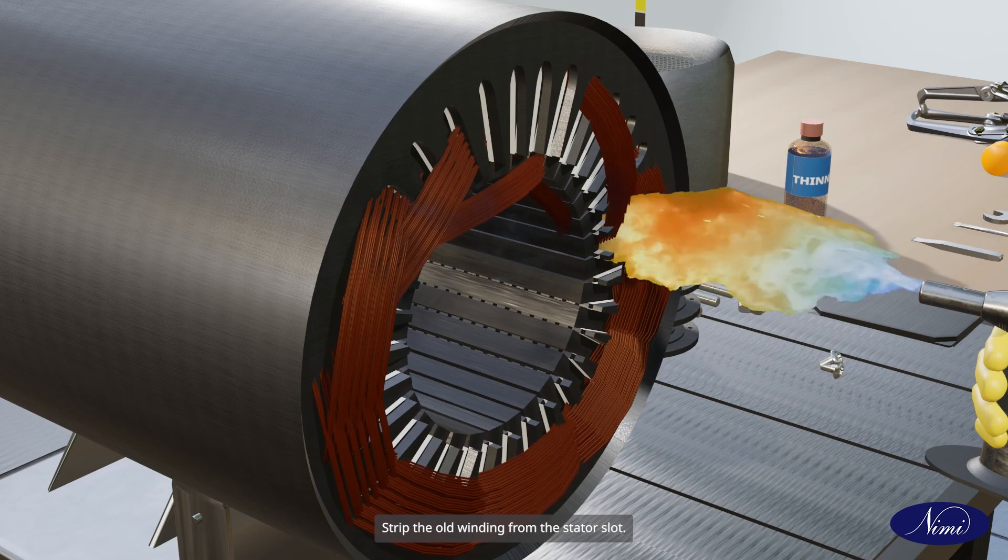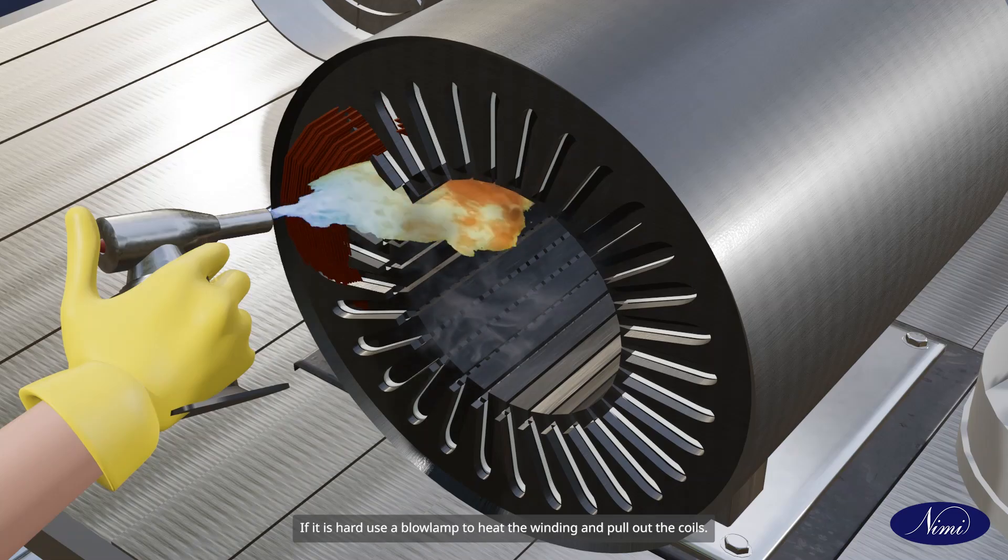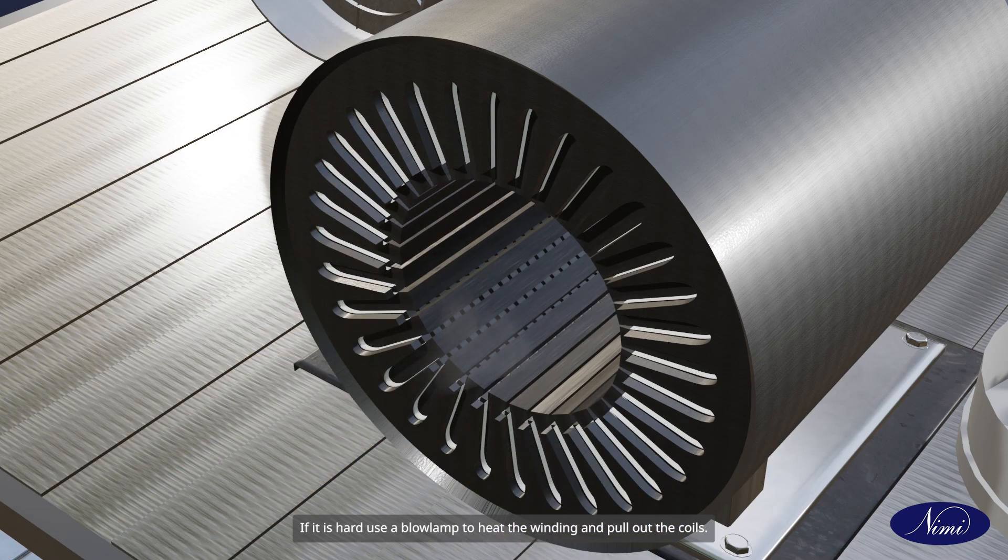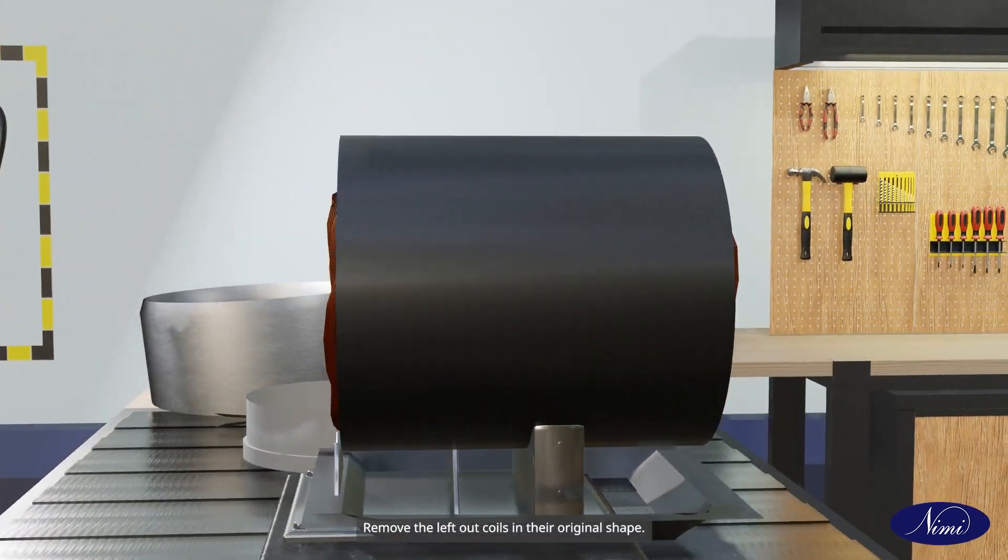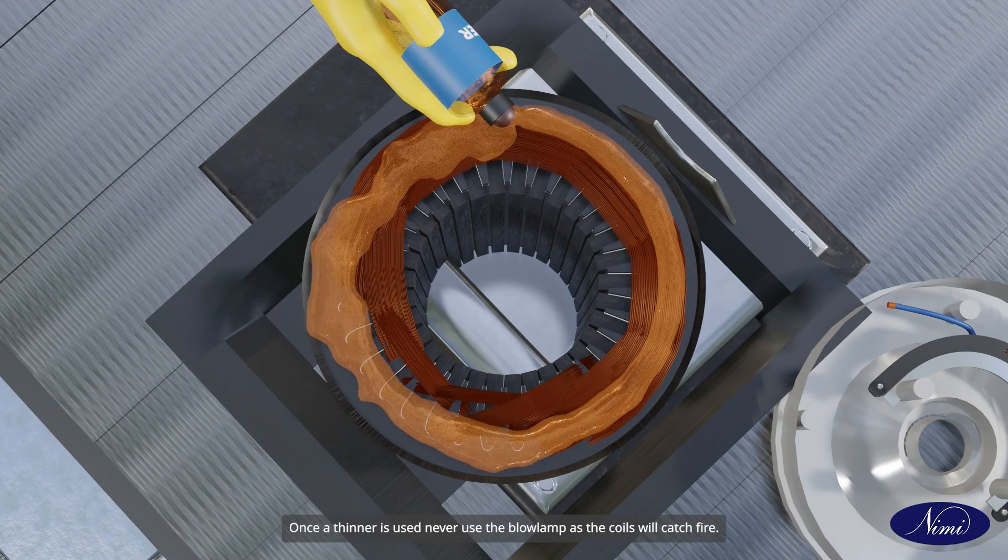Strip the old winding from the stator slot. If it is hard, use a blow lamp to heat the winding and pull out the coils. Remove the left out coils in their original shape. Use a thinner to loosen the coils. Once a thinner is used, never use the blow lamp as the coils will catch fire.